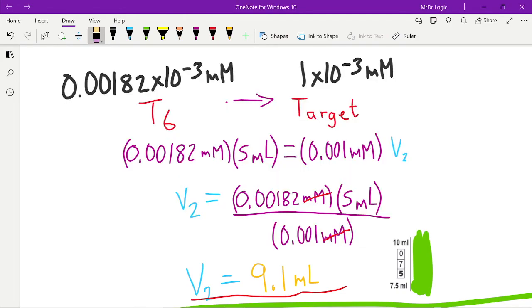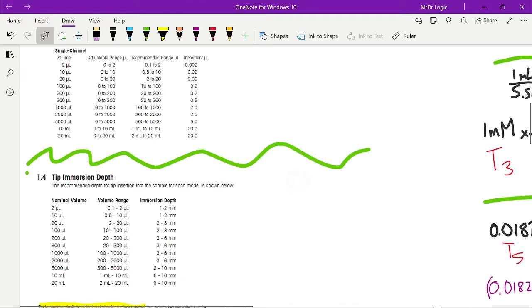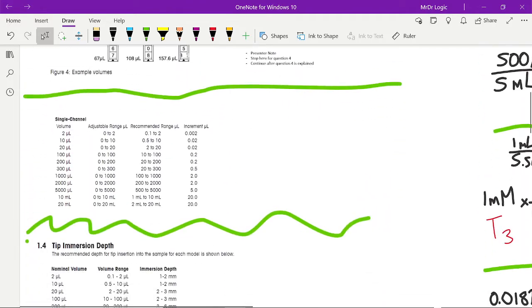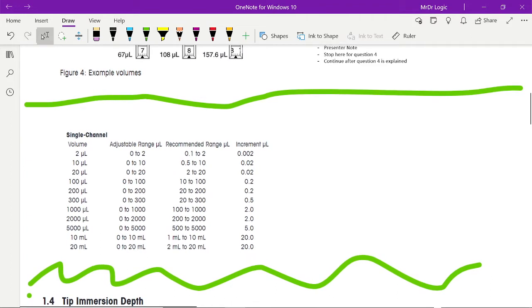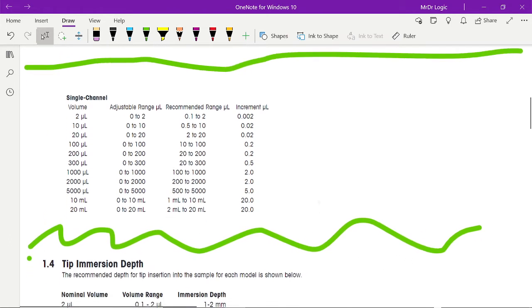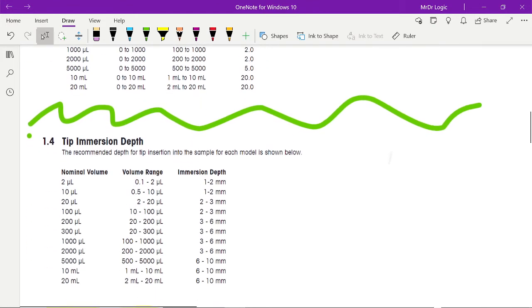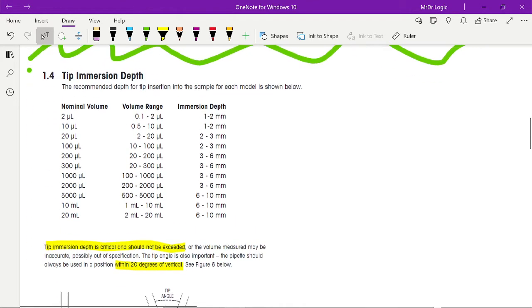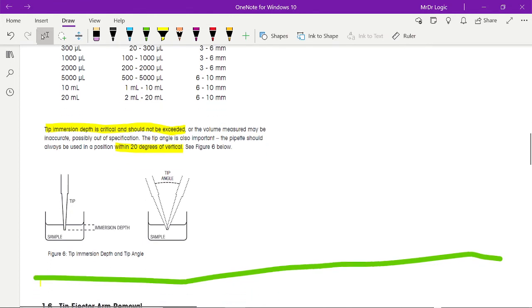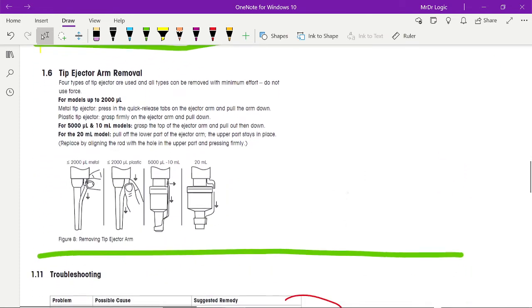Now for more of the extra stuff. This is if you're too lazy to read the PDF. So essentially, this is the recommended range of µL. This is how you return and adjust it based on what increment. This will take a long while if you're changing it by that, so I'm not really too sure of the increment µL, but who knows, who cares. So this is more about the tip immersion depth. You can literally stab it into something - well, don't stab it into your sample like you want to jab somebody, but you're going to slightly hover it over the sample. Make sure it's immersed and do it from an angle if you're afraid it's going to jump out.